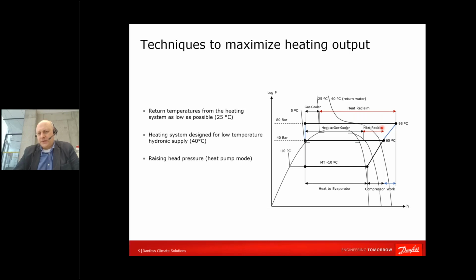Therefore, we are saying that the plant should be optimized for heat recovery, and compressors might add extra work, so the heat pump is just pushed heavier, and we can go to larger temperatures like 90 or 100 something. Yes, that will lead to higher pressure. And here we can see that if our plant is designed to deliver 25 degrees back to the heat recovery unit, our heat reclaim potential is increasing dramatically.